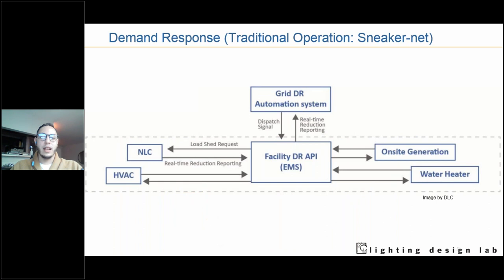What network lighting controls can do on a demand response application is allow that two-way communication, so that building that has a lot of energy being used can just tell a system, hey, reduce all your loads by 30%, and the system can tell the demand response application, hey, this is done, we are saving 30% energy across the board from our dimmed list. There's a lot more that goes into demand response, but network lighting controls can help reduce the lighting, and can also talk to HVAC or other systems to help reduce that load as well.